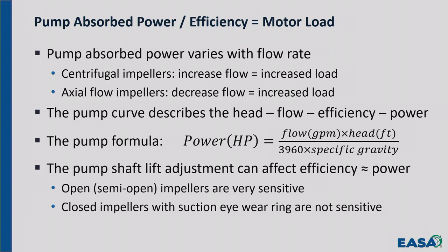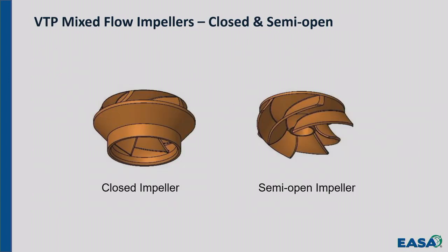Another factor that affects the load on the motor is the lift adjustment on some vertical turbine pumps. It makes a difference if that impeller is a closed impeller or a semi-open impeller or an axial flow impeller. And we'll show you some pictures of those. Okay? A closed impeller has a suction eye. The suction eye matches up with a wear ring in the stationary part of the pump, in the pump casing.